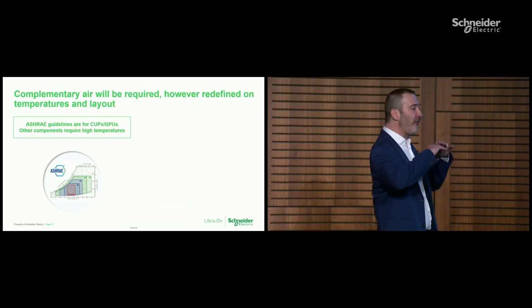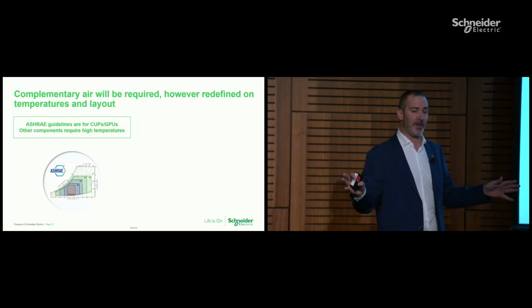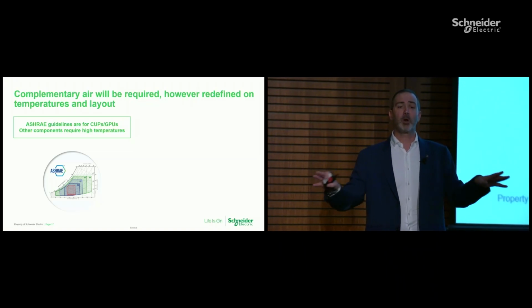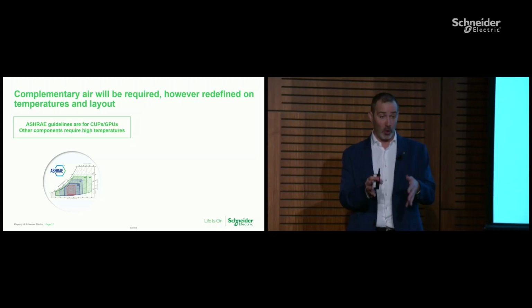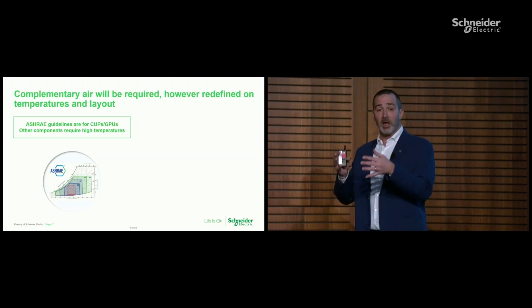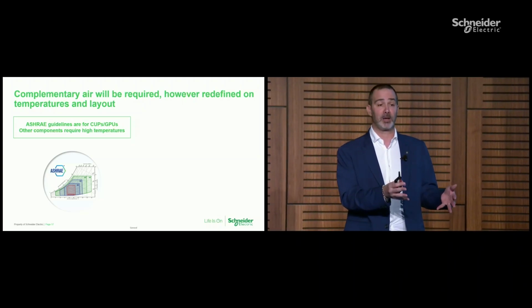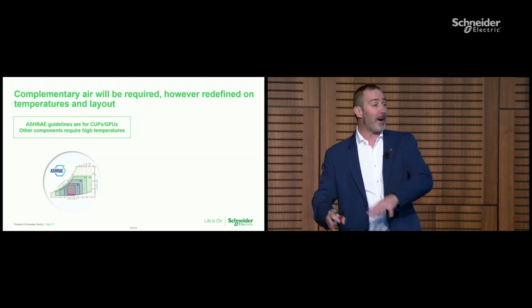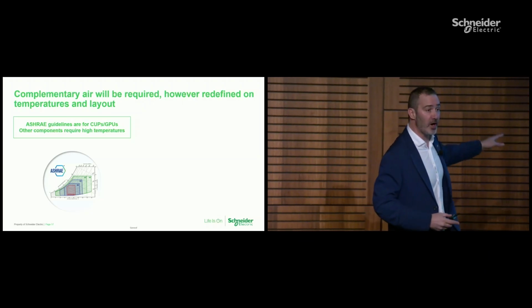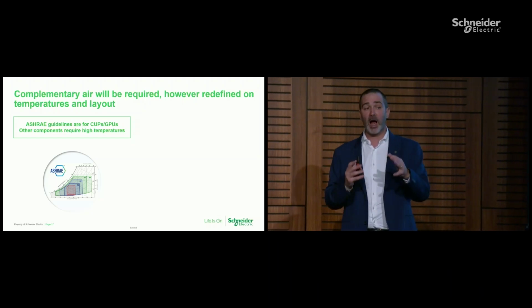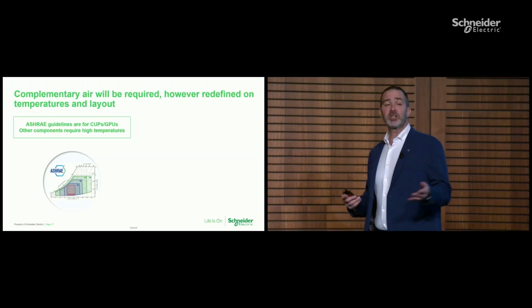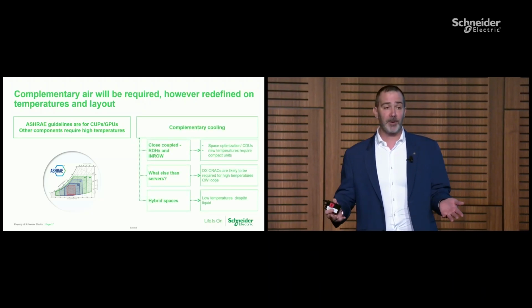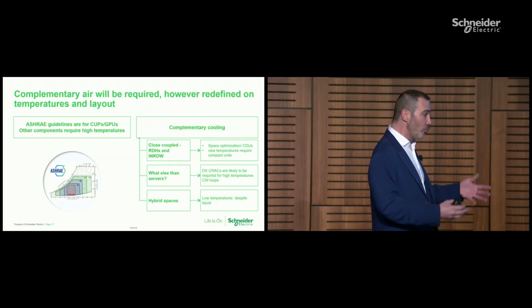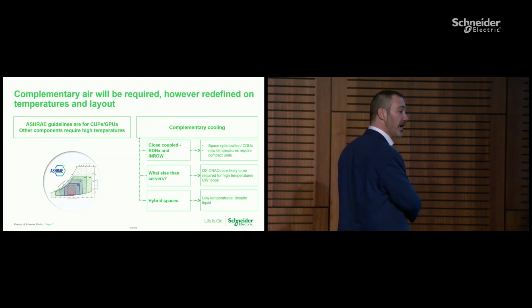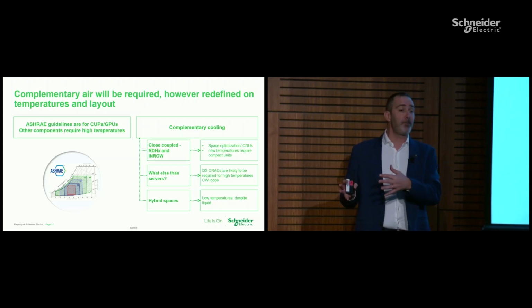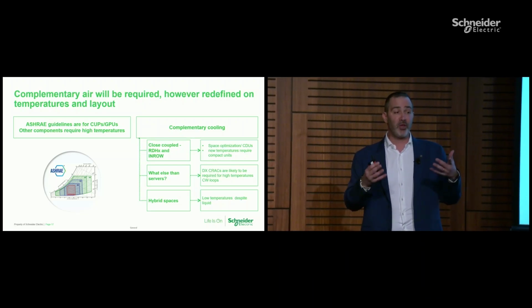Let's imagine a fully liquid deployed data center, so all the chips are liquid cooled, all of them. If so, what you need to dissipate is the thermal load of the electrical part. But the thermal load of the electrical part does not follow the ASHRAE recommendation, the ASHRAE recommendations are for the chip. So what is the water temperature there, the air temperature there? The air temperature was 27 as a supply air, but when you're looking at the electrical portion, it could be 30, could be 35.